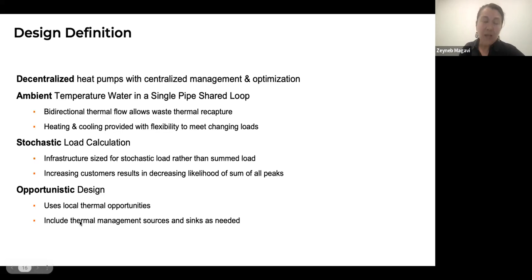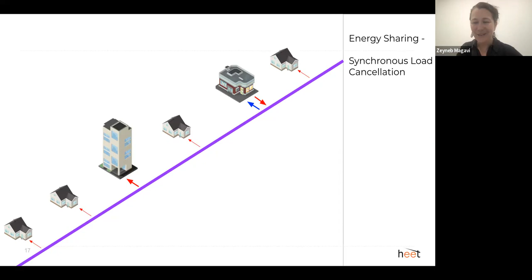So here we have an ambient temperature loop and a bunch of buildings. Here's an example. We've got, maybe it's a supermarket, maybe it's an ice rink, but it's cooling and rejecting heat, or dumping heat, into the ambient loop. I've pictured it as purple, both red and blue. And these other buildings are in heating mode and they're pulling that heat off. In this situation, you have an energy sharing that is like a new kind of energy efficiency that emerges when you do this interconnection, that would not be there with individual geothermal installs. And so this is allowing a synchronous load cancellation. If you have simultaneous heating and cooling in your district, which is often present, particularly in mixed use settings, you have this instantaneous load cancellation through the ambient loop.